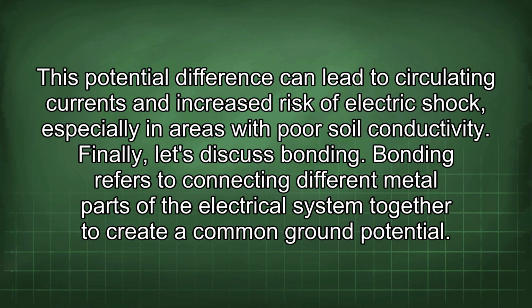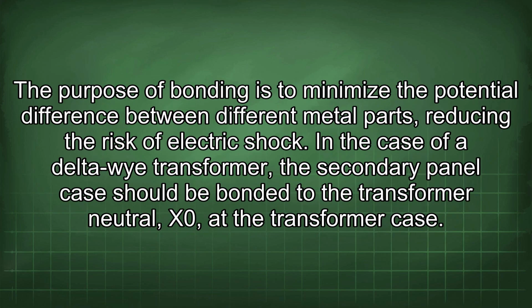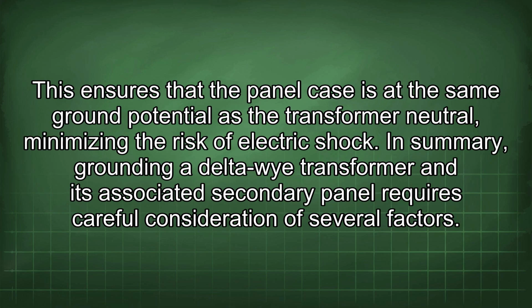Finally, let's discuss bonding. Bonding refers to connecting different metal parts of the electrical system together to create a common ground potential. The purpose of bonding is to minimize the potential difference between different metal parts, reducing the risk of electric shock. In the case of a delta-wye transformer, the secondary panel case should be bonded to the transformer neutral X0 at the transformer case. This ensures that the panel case is at the same ground potential as the transformer neutral, minimizing the risk of electric shock.